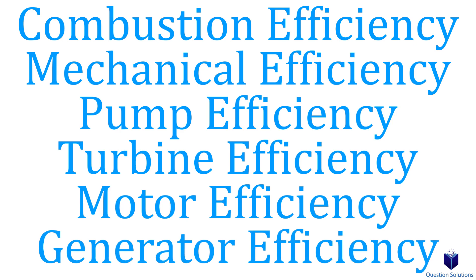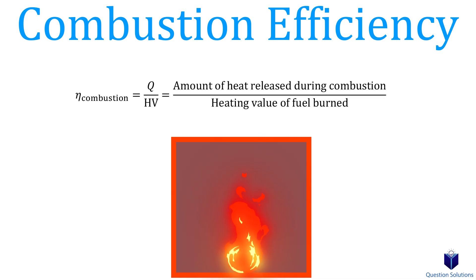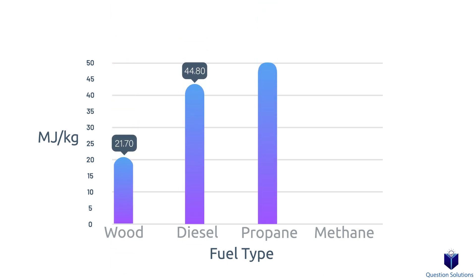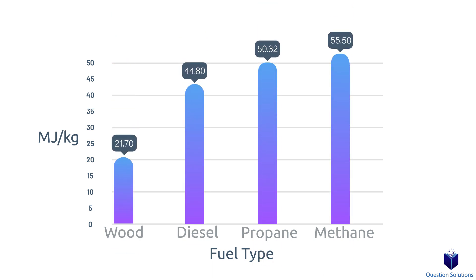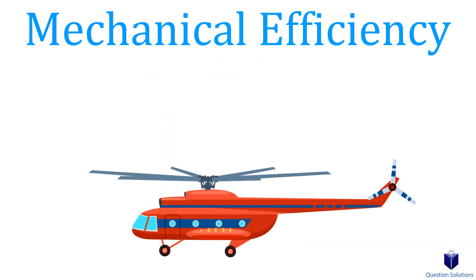Diving a bit deeper, we have different types of efficiencies. The first is combustion efficiency — that's the amount of heat released during combustion divided by the heating value of the fuel burned. The heating value of a fuel is the amount of heat released when a unit amount is burned at room temperature and the combustion products are cooled back to room temperature. If we achieve 100% combustion efficiency, the fuel is burned completely and the gases leave the combustion chamber at room temperature, meaning the heat released equals the heating value of the fuel.